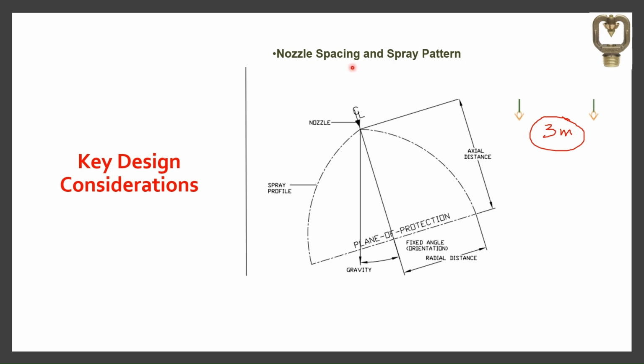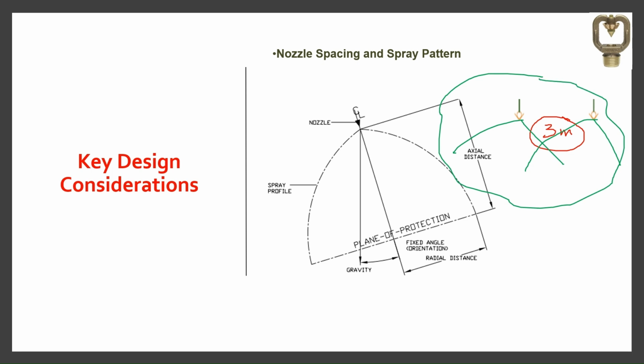So regarding the nozzle spacing, we cannot just place the nozzles randomly. As per NFPA 15, the nozzle spacing should never exceed 3 meters or 10 feet to ensure every inch is covered with water spray. And related to the spray patterns, NFPA 15 states that all the protected areas should be covered. It means, I will just reframe my words, the nozzles shall be placed in such a way that the pattern should overlap each other. So the design must ensure that these nozzles meet or overlap. Otherwise, the complete area cannot be protected.